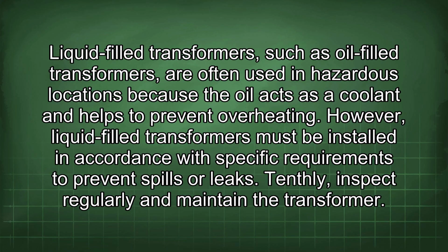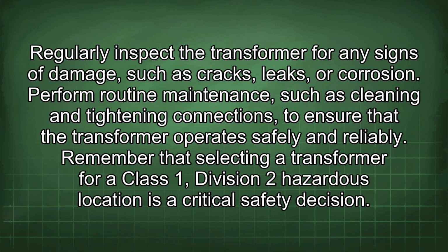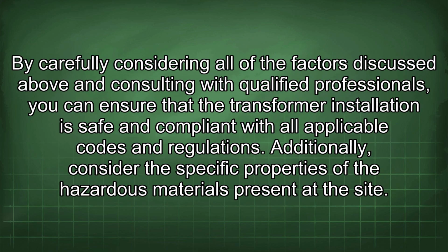Tenthly, inspect regularly and maintain the transformer. Regularly inspect the transformer for any signs of damage, such as cracks, leaks, or corrosion. Perform routine maintenance, such as cleaning and tightening connections, to ensure that the transformer operates safely and reliably. Remember that selecting a transformer for a Class 1, Division 2 hazardous location is a critical safety decision. By carefully considering all of the factors discussed above and consulting with qualified professionals, you can ensure that the transformer installation is safe and compliant with all applicable codes and regulations.